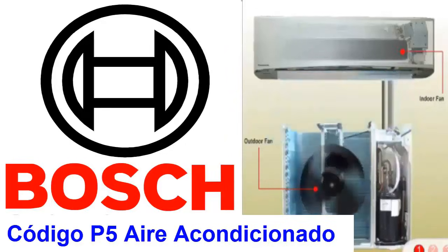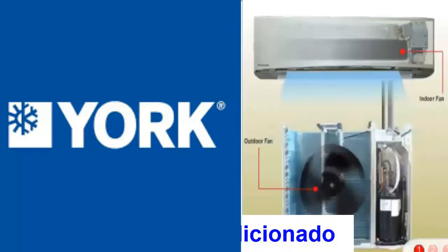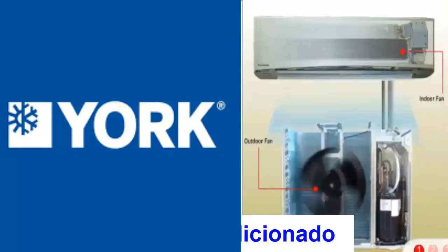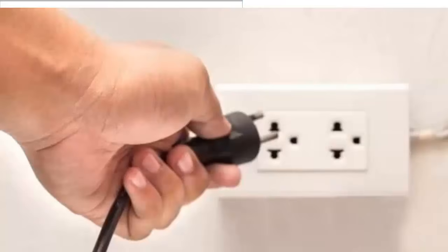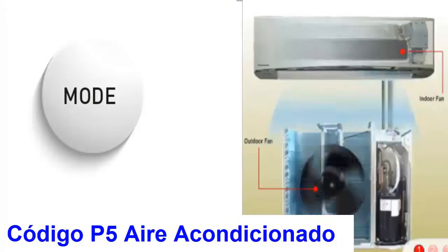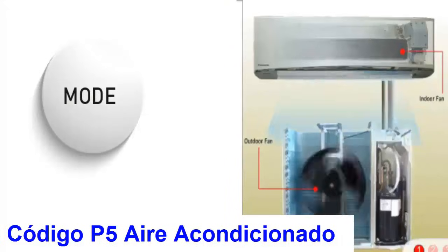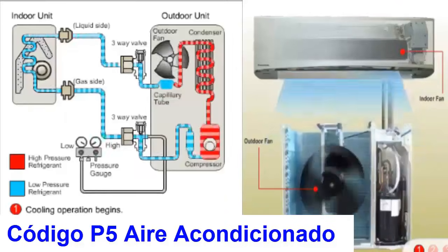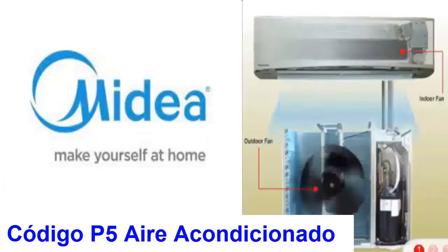6. For Bosch and York, in these cases, the P5 code indicates a mode conflict between indoor units in systems with multiple indoor units. It is recommended to disconnect the electricity from the equipment for several minutes and check if the problem persists. It is recommended to verify the settings and operating modes to ensure all units are correctly synchronized.